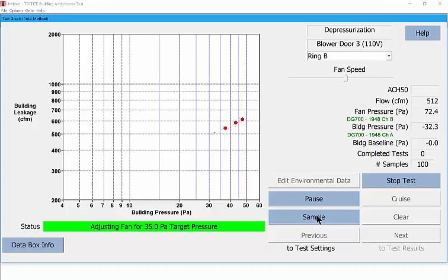And the advantage to doing a multi-point test is you'll get a lot better data because you're gathering data at a lot of different pressures, and it's doing a calculation based on all of that data it's taken, and so it does give you better information. You'll also know when you're done with the test how good your data was. It'll tell you the plus or minus on how accurate it was, and it will tell you how well all of that data fits on a line.